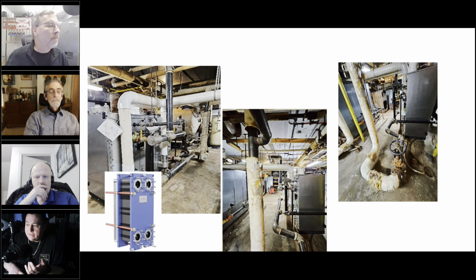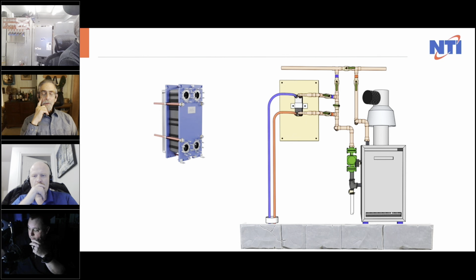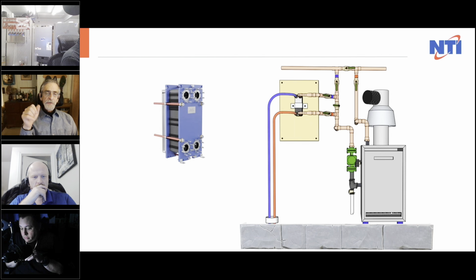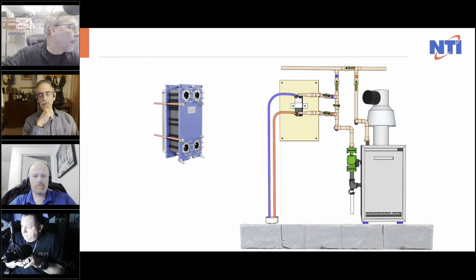One other thought, Jason - in favor of the heat exchanger, not only are you potentially solving air problems, but when you look at a system like that, you see how much old iron pipe there is. I don't care how much you flush it, eventually it's going to clog those boilers up. There's just too much crap. The heat exchanger will dramatically increase the longevity of the boiler.